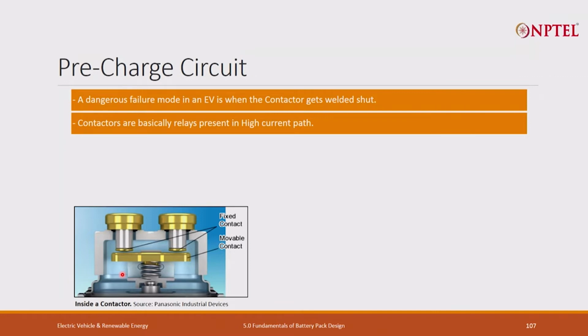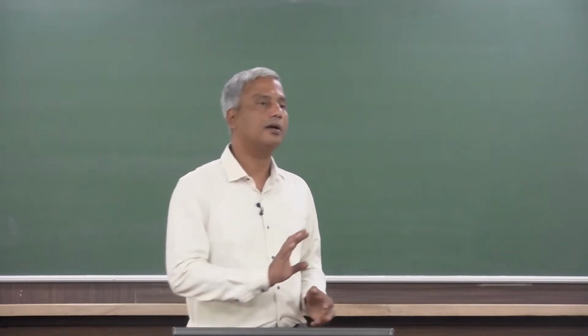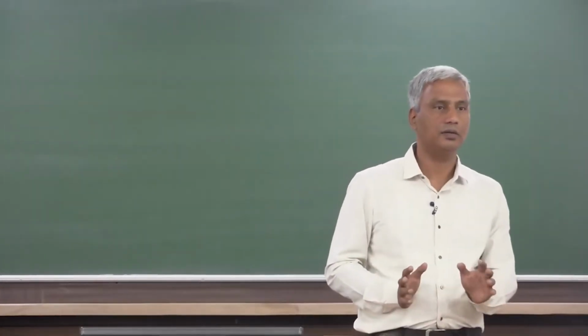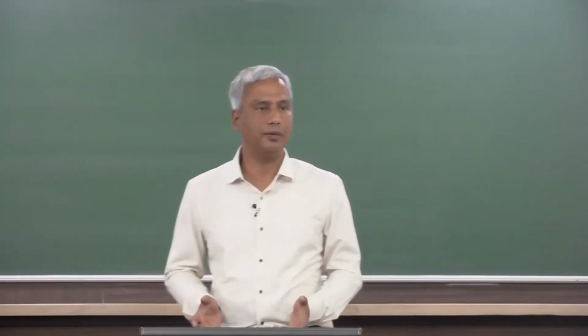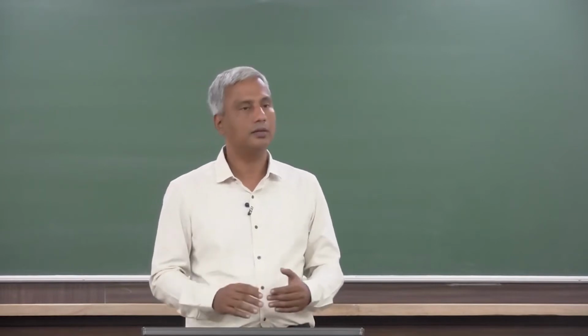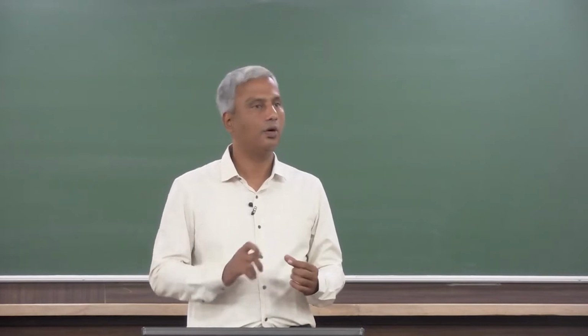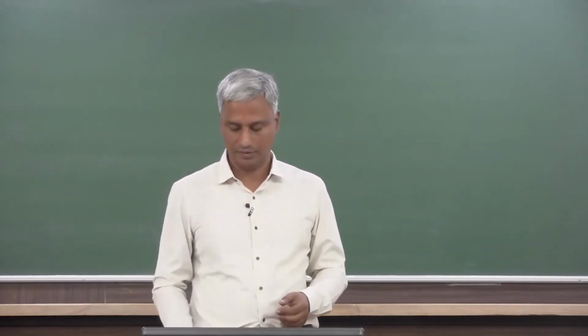We provide two parallel paths. One path is a low resistance path and the other path is a high resistance path. So we close only the high resistance path first so that the voltage comes near to the source. And once the voltage has come near to the source, then we close the low resistance path so that current within the limit flows. Otherwise, if initially we close the low resistance path, then huge inrush current will flow, and that could affect an electronic semiconductor switch, or a contactor or relay type of switch, by local welding or huge thermal stress.